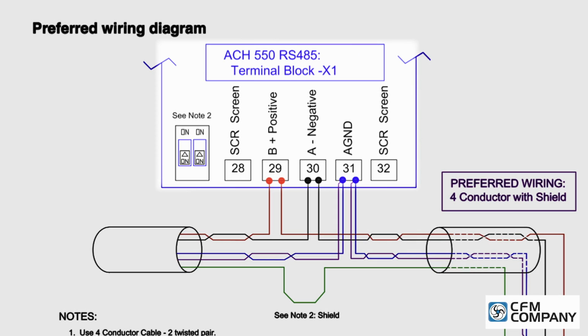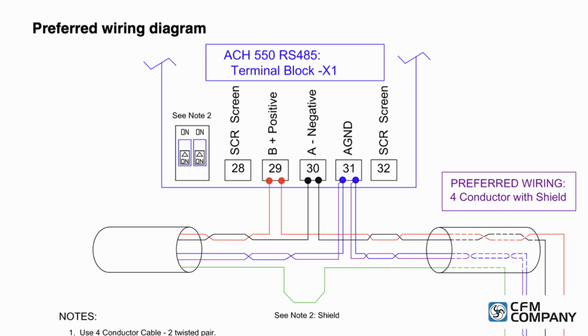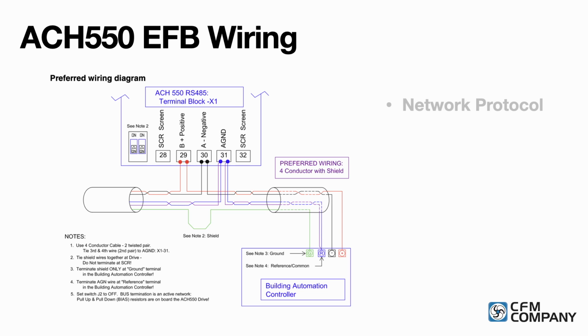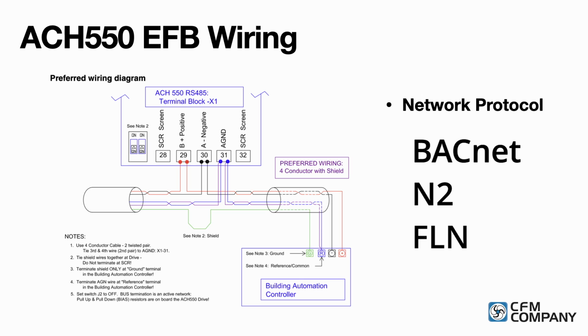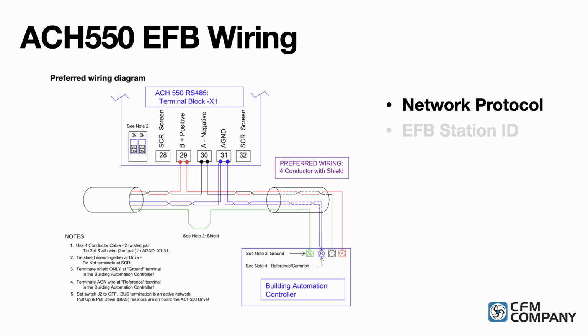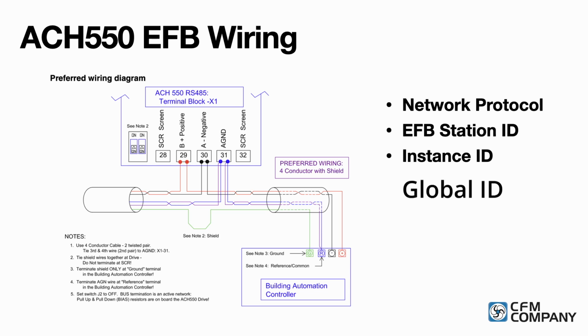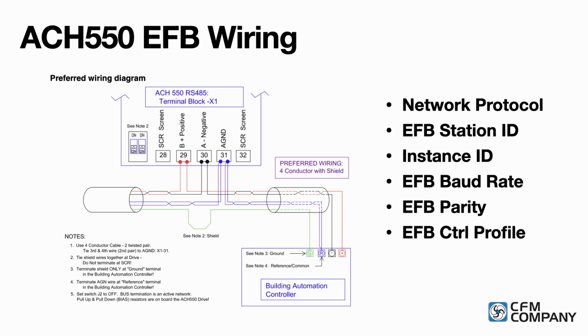If there are serial communications wires landed on the original drive, make sure to note the wire color and polarity. Find out the network information for the drive, such as network protocol, BACnet, Johnson N2, Siemens FLN, or Modbus. The EFB station ID, also known as the MAC address. The global address, also known as the instance ID. The EFB baud rate, the EFB parity, and the EFB control profile.